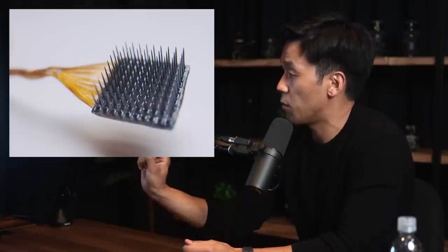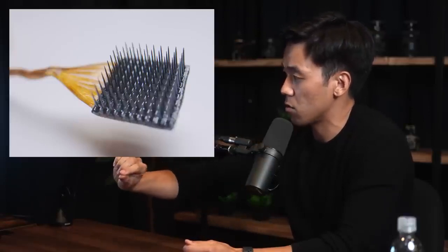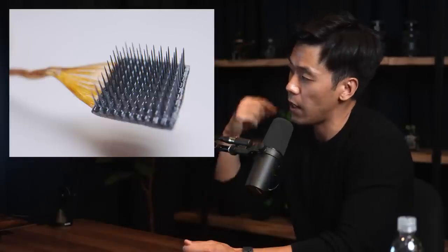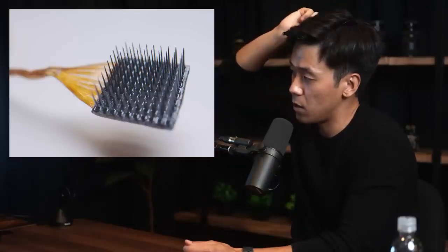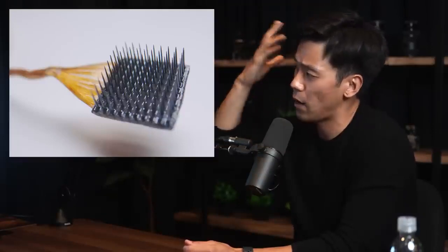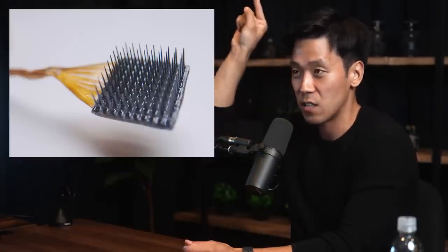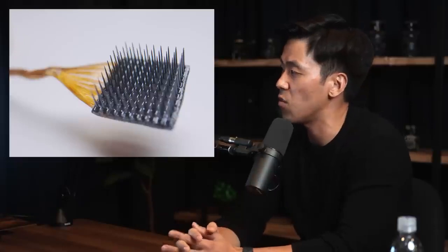And then the main key difference is the fact that there's no active electronics. These are just electrodes, and then there's a bundle of wire that you're seeing, and that then exits the craniectomy and has this port that you can connect to for any external electronic devices. They are working on, or have, a wireless telemetry device, but it still requires a through-the-skin port that is one of the biggest failure modes for infection for the system.